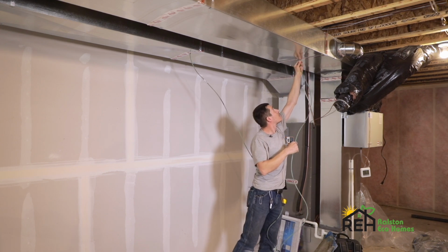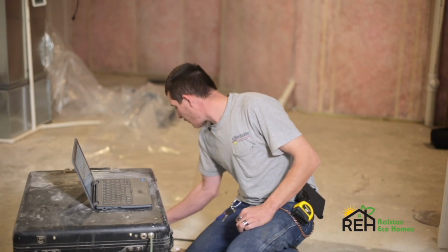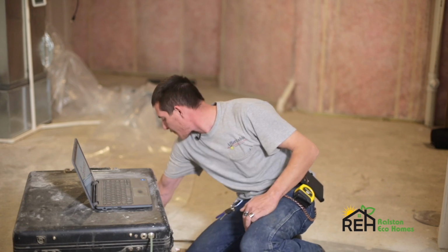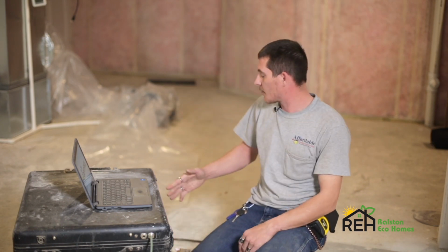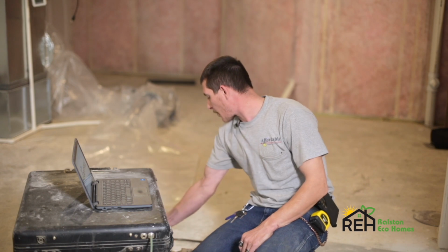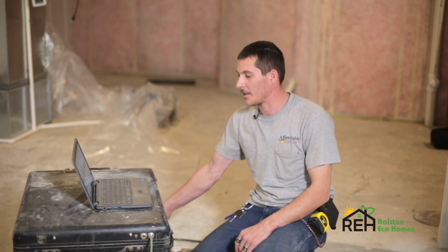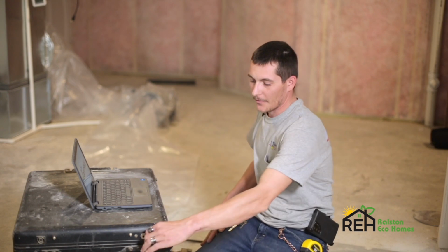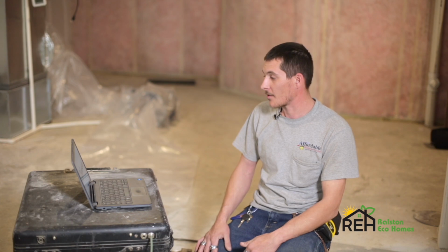We're putting pressure to the system, and as the system is pressurized, the reference hoses are sending it back to the computer, telling us how much leakage there is, and we'll be able to gradually watch it seal, and the pressure will go up, which will give us different numbers to show us that our leakage is going down. So we're just gonna hook up the air hose to the front of it, because we use compressed air to release the glue into the system. And then we'll hook up our cords here that give the heaters power and the computer itself power. And then we've got the reference hose in the back that we've already connected up to the furnace. And then the next step is just to turn on the system and let it load, and then we can get into the AeroSeal program.